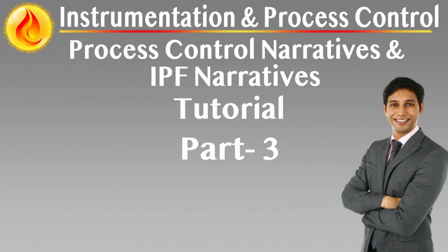Narrative structure for each alarm. Each alarm narrative contains the following elements. Purpose of the alarm describes the process condition being monitored and why the alarm exists. This includes the deviation or abnormal state the alarm is intended to signal, e.g. high temperature indicating potential fouling, low flow indicating a blockage. The purpose should not simply restate the condition, high level, but explain its relevance to process stability or equipment health.